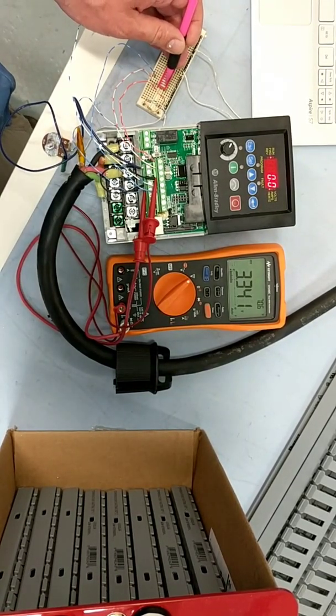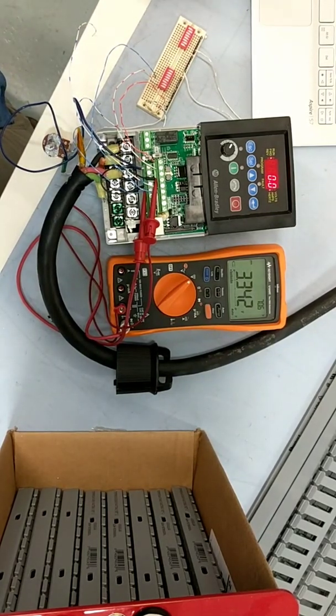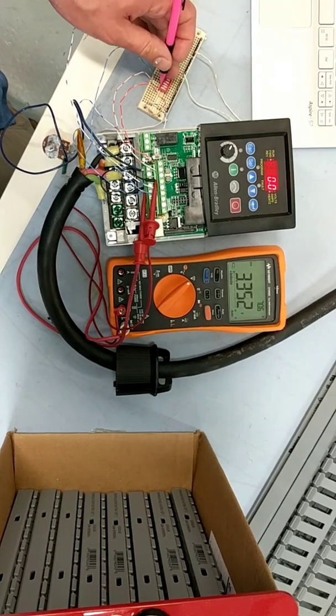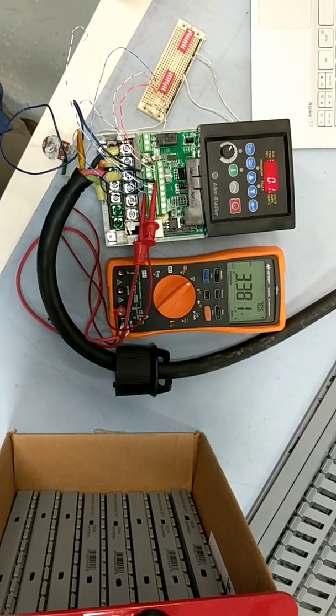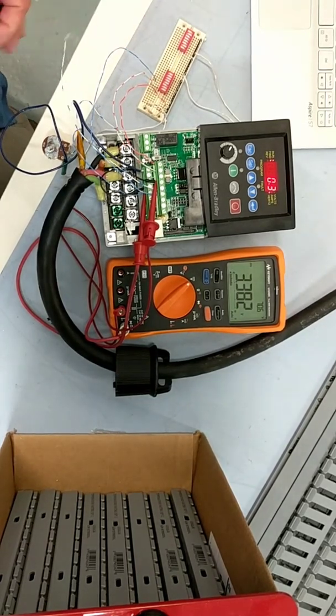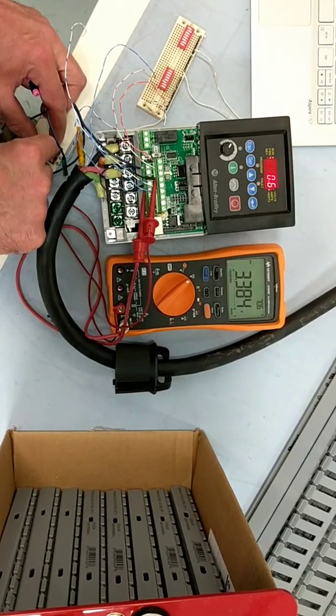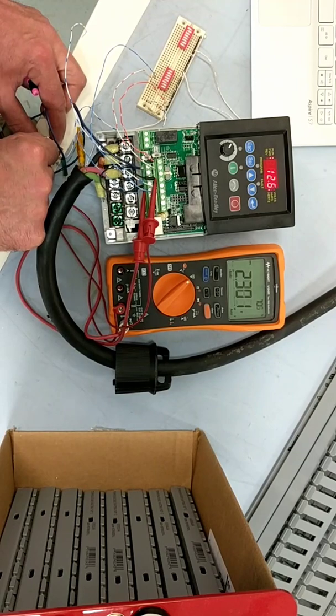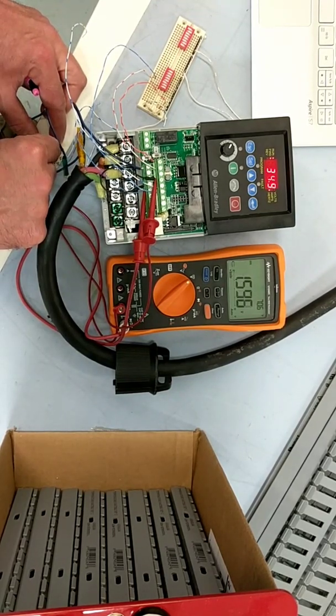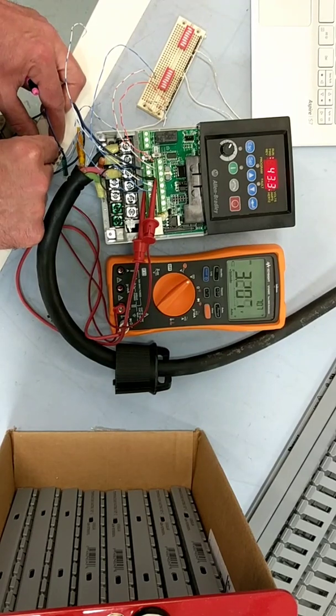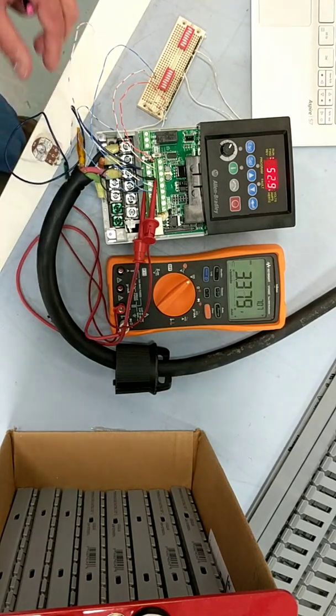First, turn on power. Drive is not active. We have to reapply the start signal. So there we go. And it's already at the set point, so I'm going to need to move that lower down to the minimum, and we see it ramping up. And now it's ramping down. It's at the maximum 20 milliamps now. And yeah, it works in both directions. Try and get it again to hover around that set point. All right, looking good.